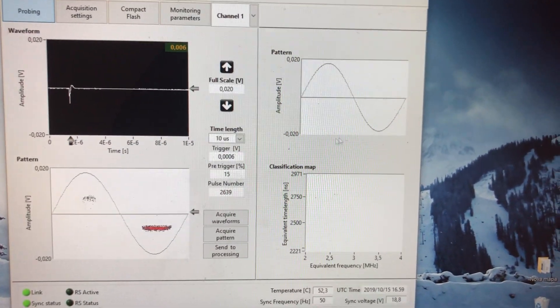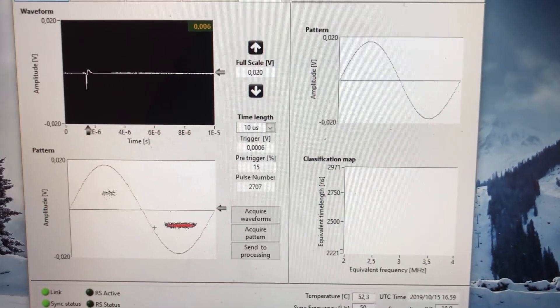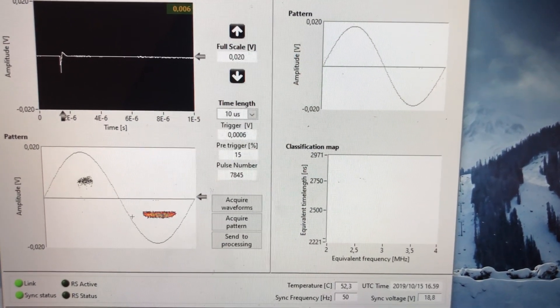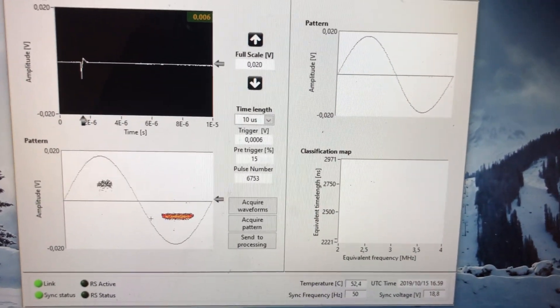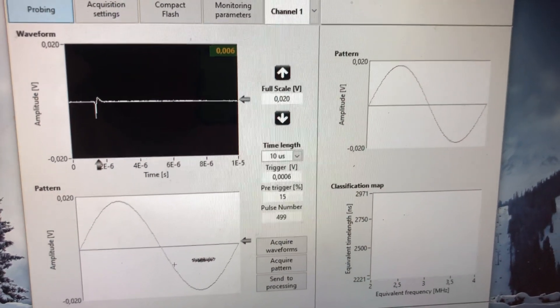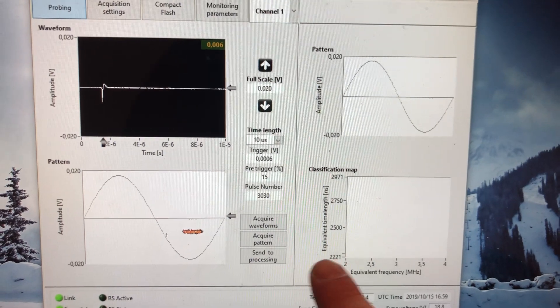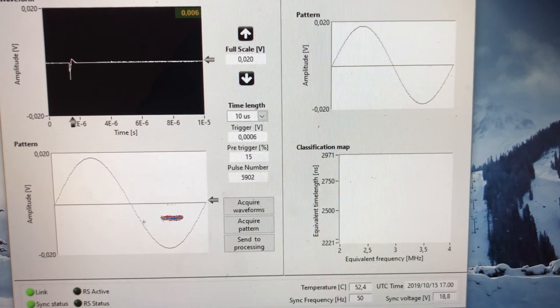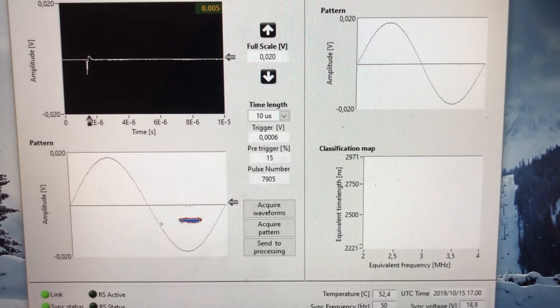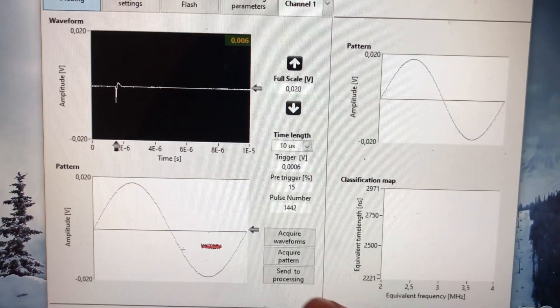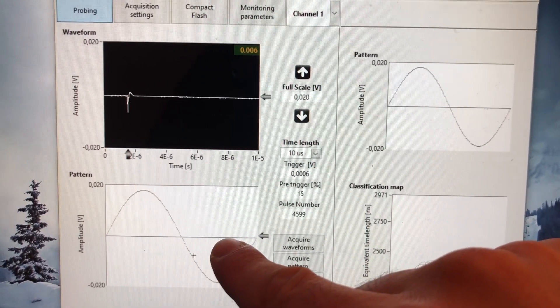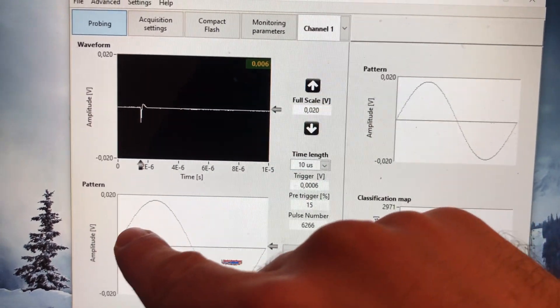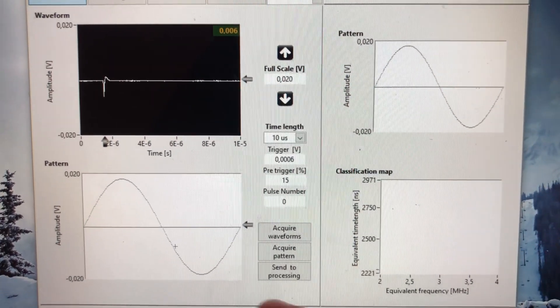Just to repeat, this is now Corona, the positive and the negative side on the positive and the negative half wave. And we know it's Corona because when I reduce the voltage and I don't have any more positive side Corona as right now, what I can say, it's markedly asymmetric. So it happens only in one half cycle. It has a quite large repetition rate, which we saw when I increased the voltage. PD magnitudes with almost no dispersion. What we can see, everything happens here amplitude wise. There's no signals here and no signals here. Everything is happening here. The same happened with the positive side Corona.